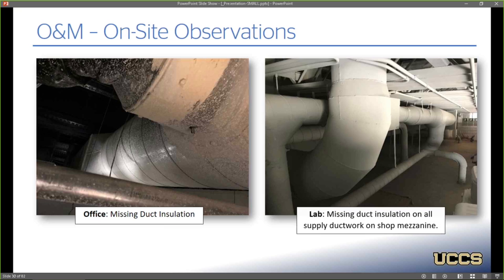And in the lab building, in the shop mezzanine is where most of that rooftop unit ductwork is routed. And that rooftop unit doesn't even serve that shop space, but all of that duct is uninsulated, which means in the summer months that's going to leach a lot of heat from that shop area and reduce the effectiveness of the cooling on that unit.